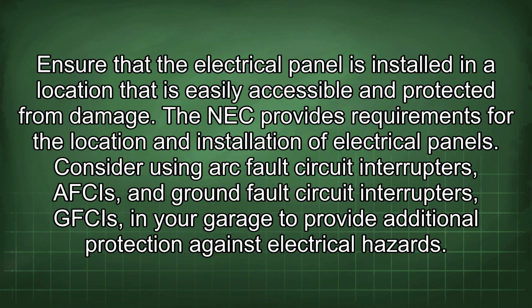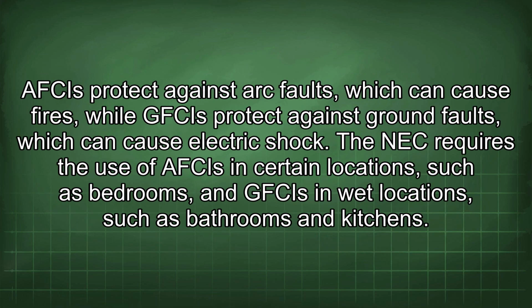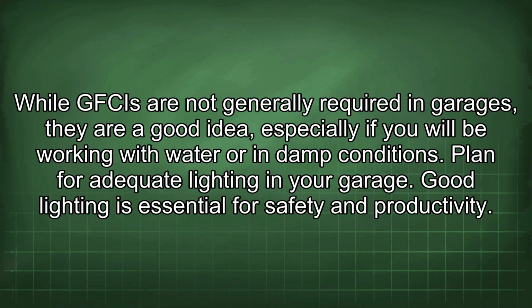Consider using arc fault circuit interrupters (AFCIs) and ground fault circuit interrupters (GFCIs) in your garage to provide additional protection against electrical hazards. AFCIs protect against arc faults, which can cause fires, while GFCIs protect against ground faults, which can cause electric shock. The NEC requires the use of AFCIs in certain locations such as bedrooms and GFCIs in wet locations such as bathrooms and kitchens. While GFCIs are not generally required in garages, they are a good idea, especially if you will be working with water or in damp conditions.